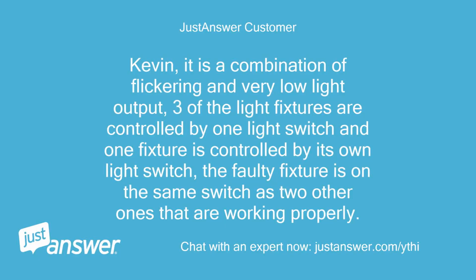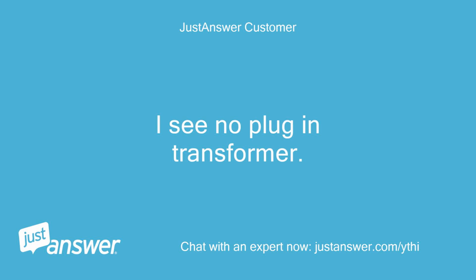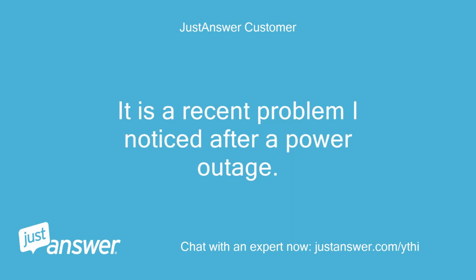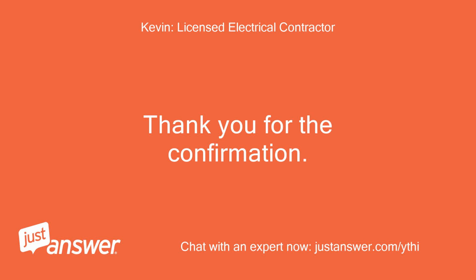Kevin, it is a combination of flickering and very low light output. 3 of the light fixtures are controlled by one light switch and one fixture is controlled by its own light switch. The faulty fixture is on the same switch as 2 other ones that are working properly. I see no plug-in transformer. It is a recent problem I noticed after a power outage. Thank you for the confirmation.